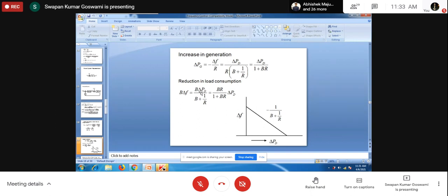As there is increased current flow from the generator, the output torque will increase, while the input torque remains the same. So what will happen? There will be a decelerating force. Because of this decelerating force, the speed starts decreasing. The speed has not decreased much, but as it starts decreasing, there will be a release of kinetic energy by the system, and that kinetic energy alone will then be supplying the power to the load.